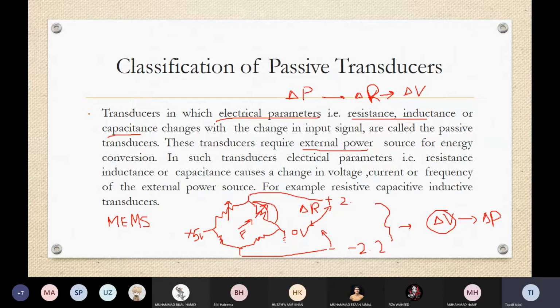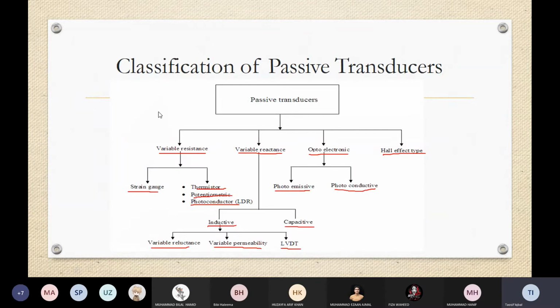So upon application of pressure, the resistance is basically in the form of a membrane. When pressure is applied, the membrane deforms, and that deformation changes the resistance. Therefore, that change of resistance is translated into voltage, and from the voltage we detect the actual pressure. So passive transducers are of different types: variable resistance, variable reactance, optoelectronic, Hall effect, and so on. The further types of passive transducers are variable resistance type, reactance type, and capacitance type.